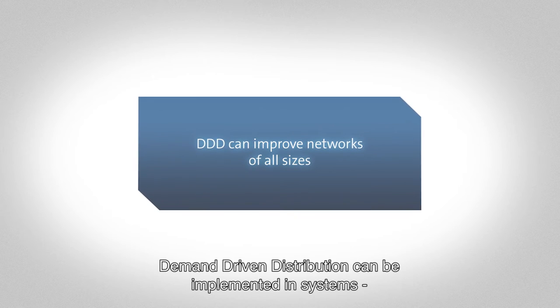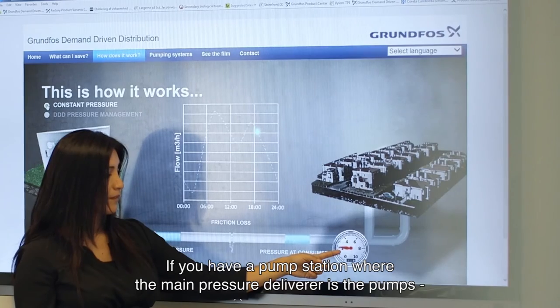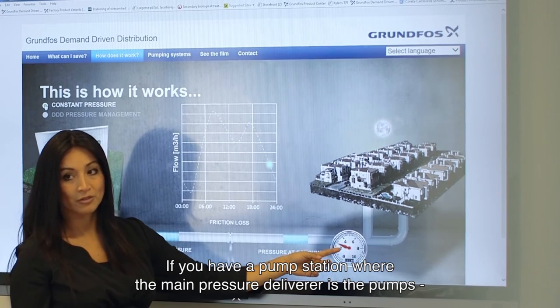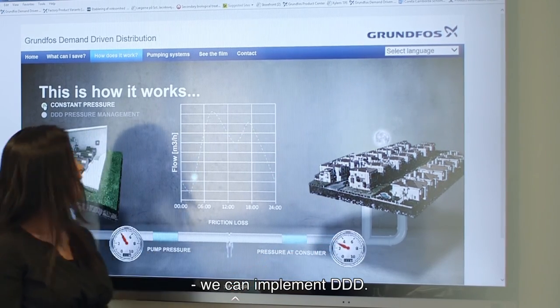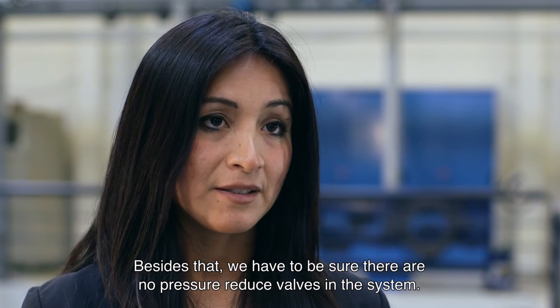Demand Driven Distribution can be implemented in systems where the pressure required for the network is delivered by pumping. If you have a pump station where the main pressure delivered is from the pumps, we can implement DDD. Besides that, we have to be sure there are no pressure-reducing valves in the system.